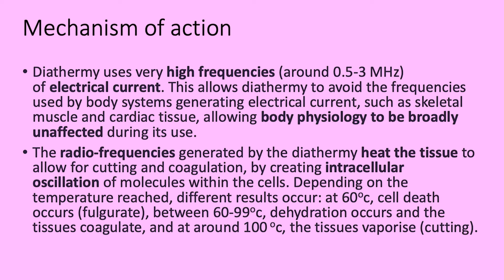That is about 500,000 hertz to 3 million hertz. This allows diathermy to avoid frequencies used by body systems generating electrical currents, such as skeletal muscle and cardiac tissue, allowing body physiology to be broadly unaffected by its use. The radio frequencies generated by diathermy heat the tissue to allow for cutting and coagulation.